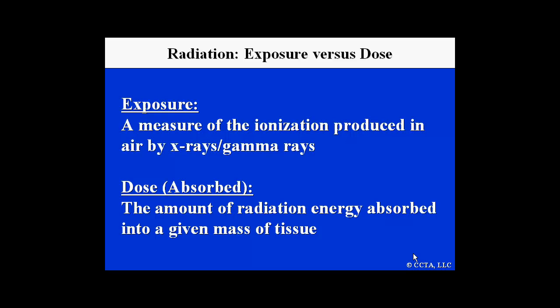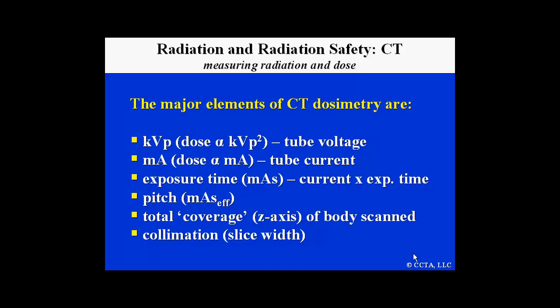Dose, or absorbed dose, is the amount of radiation energy absorbed into a given mass of tissue. The major elements of CT dosimetry include tube voltage, or kilovolts. Importantly, radiation dose is related to kilovolt squared, so this is a very important parameter in terms of either increasing or reducing radiation dose.